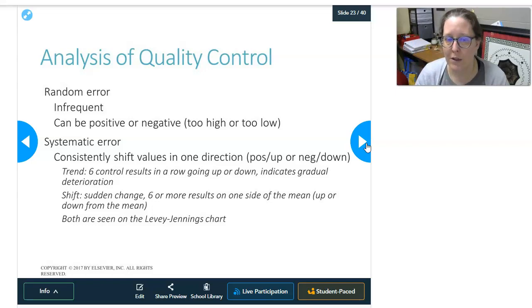And within those, there are both trends and shifts. So trends look almost like a stair step. It's trending up. So you have 6 controls in a row that are either going up or going down. Okay. And it usually indicates some kind of gradual deterioration. Maybe your reagents are going bad, or the lamp's starting to go bad, or something like that. But it usually indicates a problem with the machine, the calibrator, the reagent, or something like that. It could also be deterioration of the controls themselves.